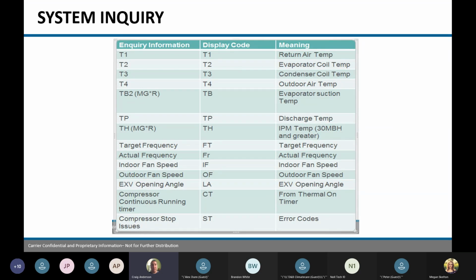So while the unit is running, we can actually see what the return air temperature is going to that unit. What's your evaporator coil temperature, your outdoor coil temperature, outdoor air temperature. So that gives you some ideas if something weird is going on. If the outdoor air temperature sensor is not working, we have a pocket thermometer out there. It says it's 40 degrees, and if we look at the remote, that sensor is saying it's 80 degrees. So hey, we know something is going on. It's getting extra heat from somewhere. So this is just a little background on what you can do when looking at a unit and seeing what it's doing. It's all in the manual for the remote where it would tell you to get into the system inquiries.